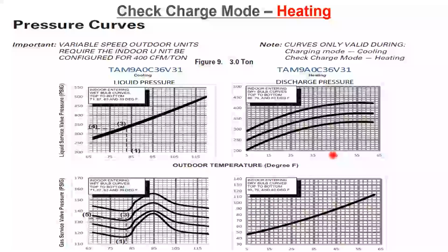And then 45 degrees, and you have this line 60, middle line 70, top line represents 80 degrees indoor. So if you have a 70 degree indoor, reference the middle line, 45, it intersects with the middle line, your head pressure should be about 360. So we're going to get them as close as possible to the pressure curves. And again, in October, right before heating season, I'll go deeper into using the pressure curves so everybody can get savvy with using the pressure curves.